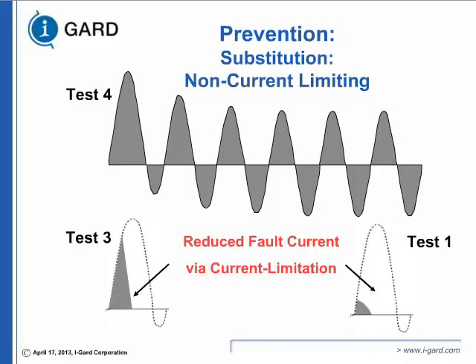I mentioned that they reduce the energy. You can see that if it's a non-current limiting fuse, you see Test 4 on the top. The colored area denotes how much energy there was. If you can count, you'll notice it's close to 6 cycles or so before it interrupts. Test 3, it interrupts in half a cycle or less. Test 1, it interrupted even quicker. Now, UL defines that a device can only be classified as current limiting if the clearing time is half a cycle or less, because it reaches the peak at that time. Most of the devices will clear faster than that.